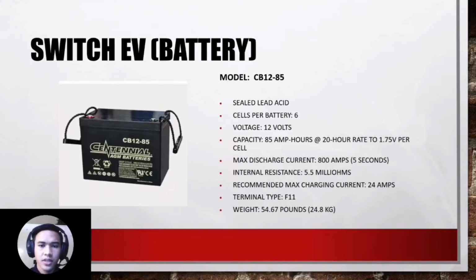The voltage of this battery is 12 volts. Its capacity is 85 amp hours, or 20 hour rate to 1.75 volts per cell. The max discharge current is 800 amps in 5 seconds, and the internal resistance is 5.5 milliohms.